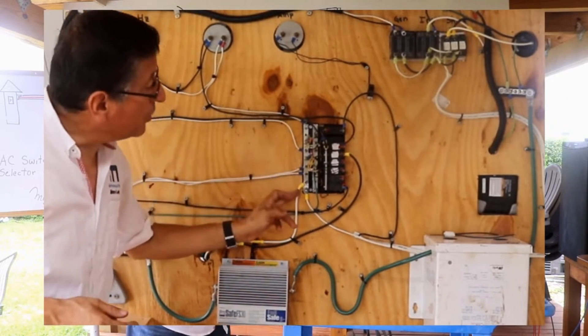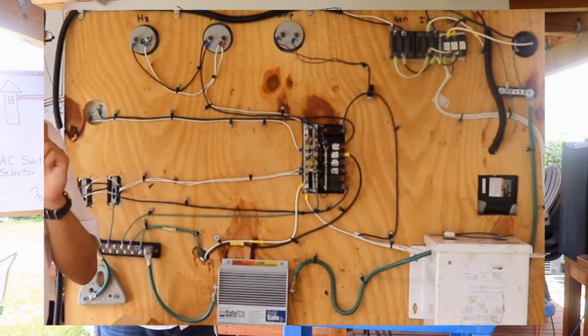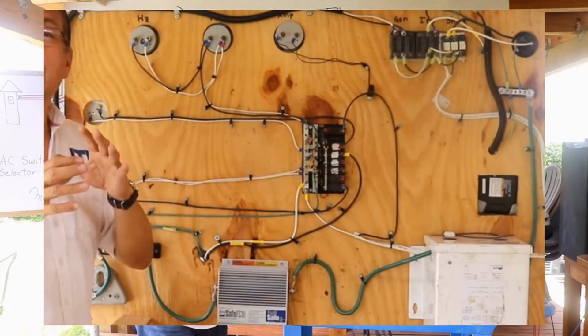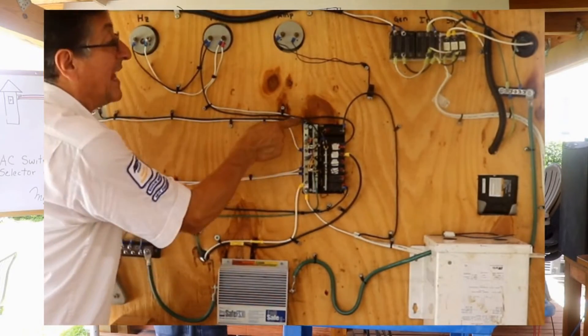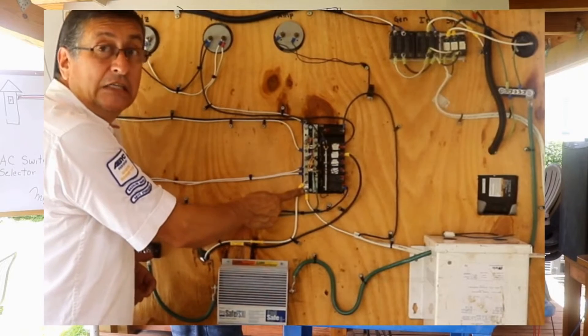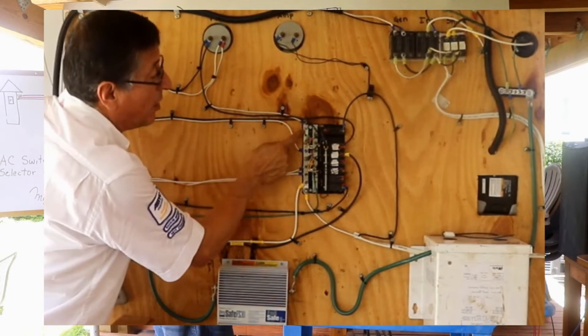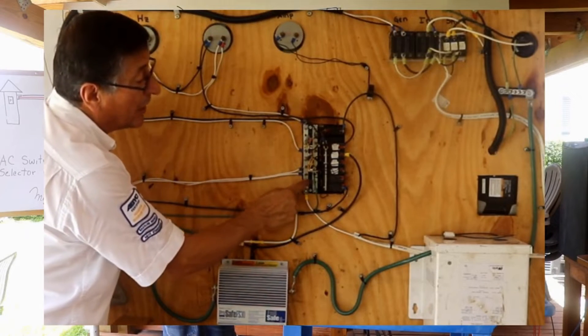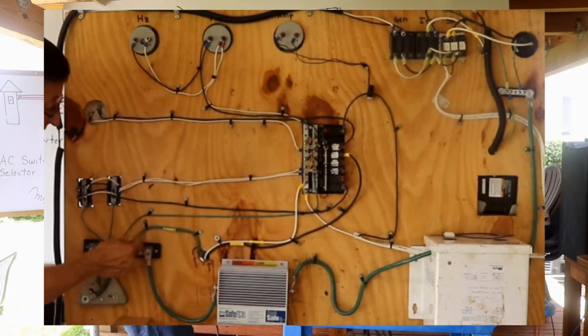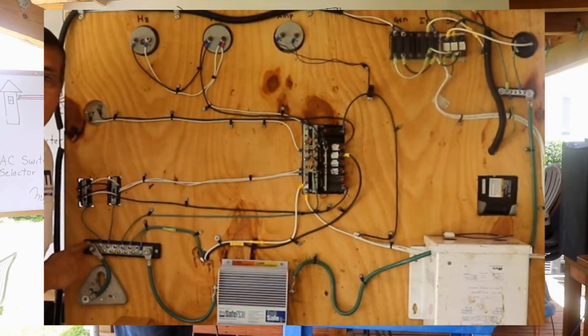Separated bus bar for neutral and separated bus bar for ground — never put together. If somebody enters the boat and installs other equipment connecting neutral with ground, and this one is now hot, it's catastrophic. If the neutral is hot and you suddenly connect the neutral with the ground, the ground — the bonding — is now hot at 120V.